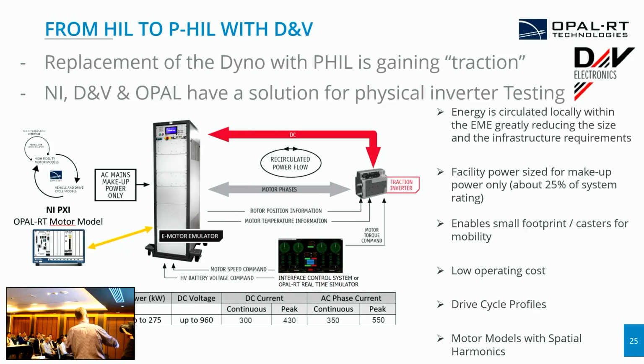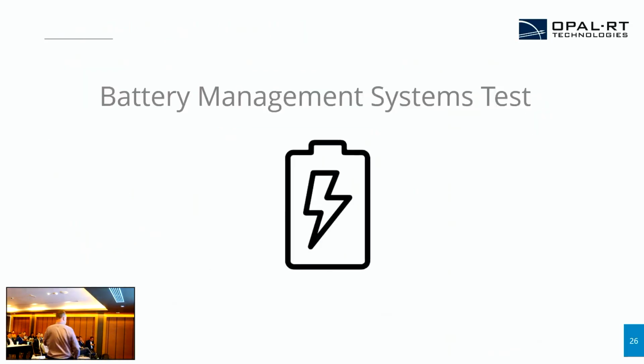We have our simulator connected to a big amplifier. This simulates 1000 volts or 300, 400 ampere, where you're testing a real inverter. So here we're not only testing the inverter model or device, we're testing the real inverter - this is another level of testing. Of course, if you're in university, it may be academic, but if you're a real manufacturer, this needs to be done eventually. So this is what we're able to achieve.